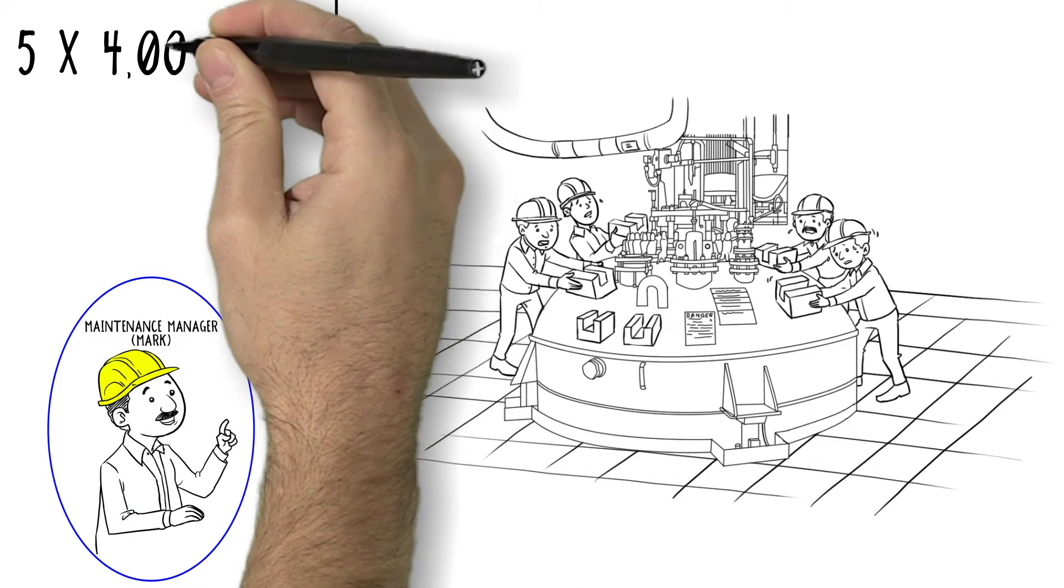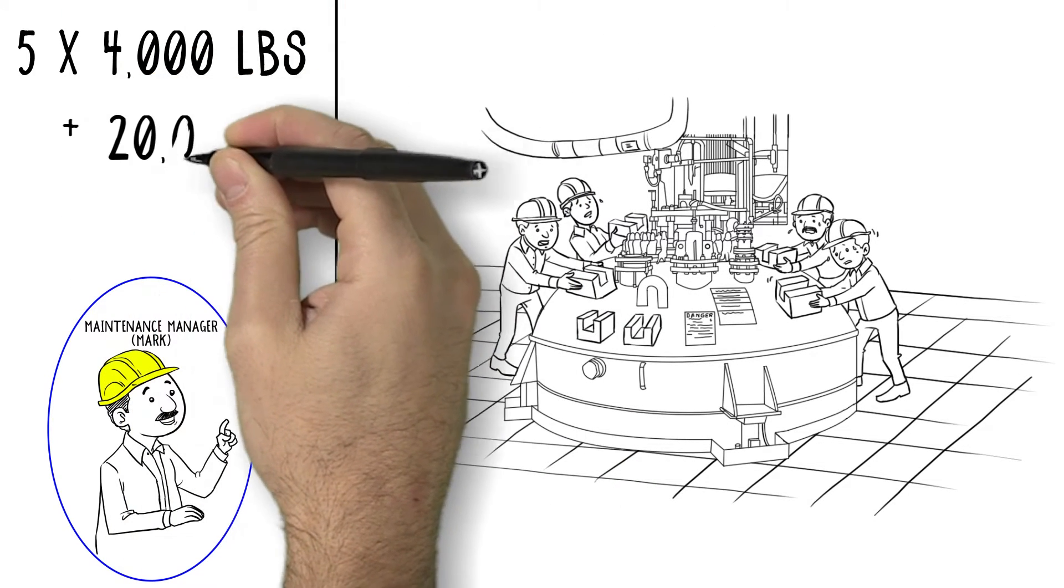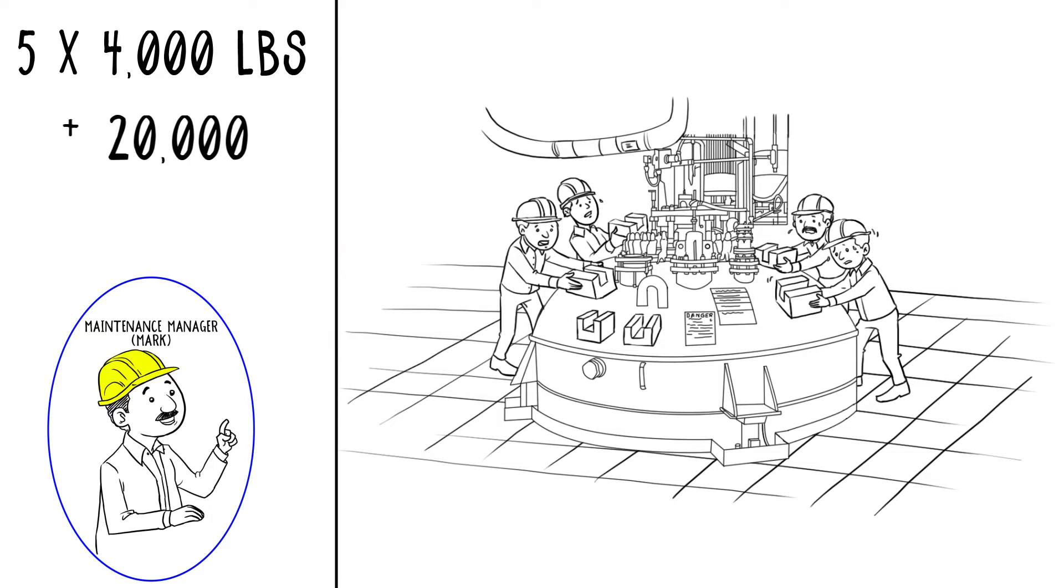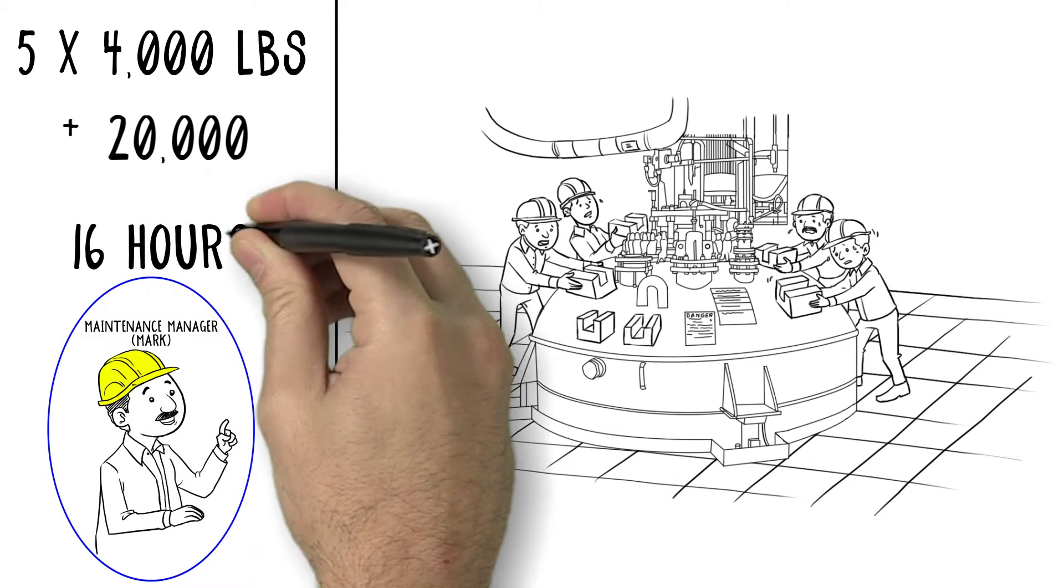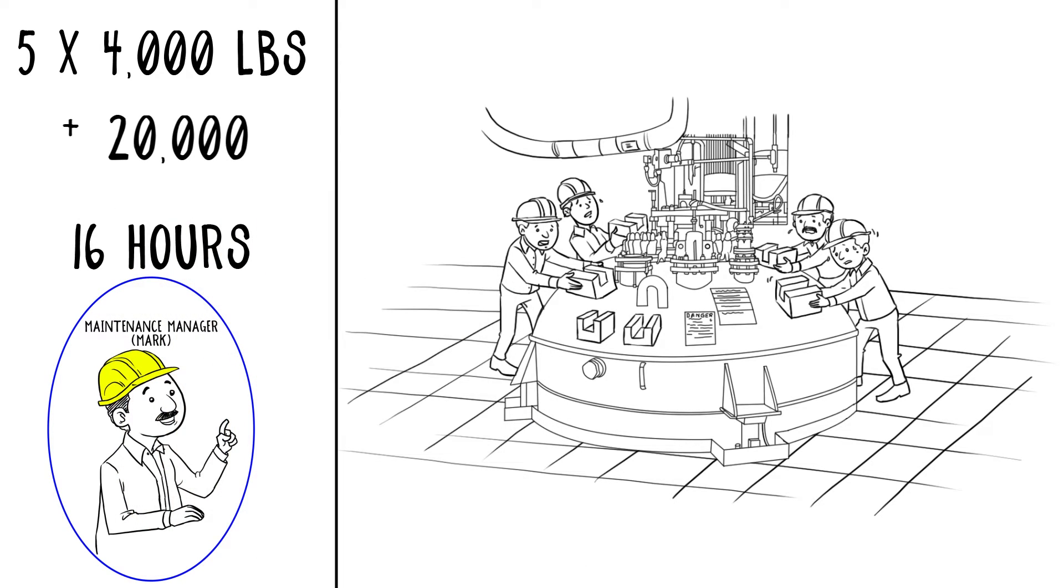There were five 4,000-pound scales and one 20,000-pound scale in each system. It takes us 16 hours to load test weights, calibrate, and validate all five scales. We have to load and unload the test weights, which takes time and raises safety concerns. It can't be rushed.